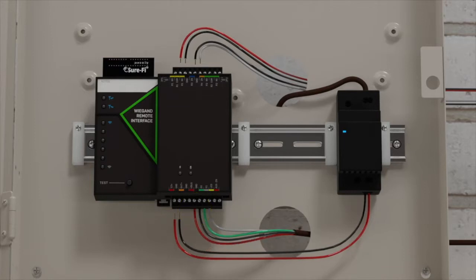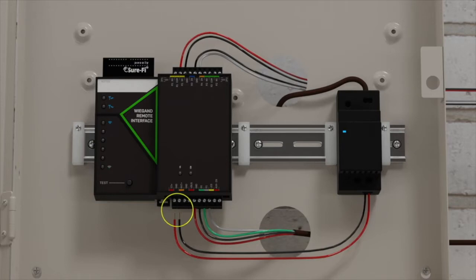Connect the gate controller relays to either of the relay outputs on the top of the remote interface, R1 or R2. For a gate operator, use the terminals normally open and common for a dry relay contact. Connect 12 volts DC power.